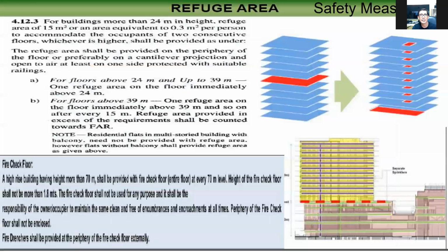So in designing buildings, in designing high-rise buildings, there is what you call the refuge area. For buildings more than 24 meters in height, a refuge area of 15 square meters, or an equivalent of 0.3 square meter per person to accommodate occupants of 2 consecutive floors, whichever is higher, shall be provided. This shall be on the periphery of the floor or preferably on a cantilever projection, open to air at least on one side and protected with suitable railings.